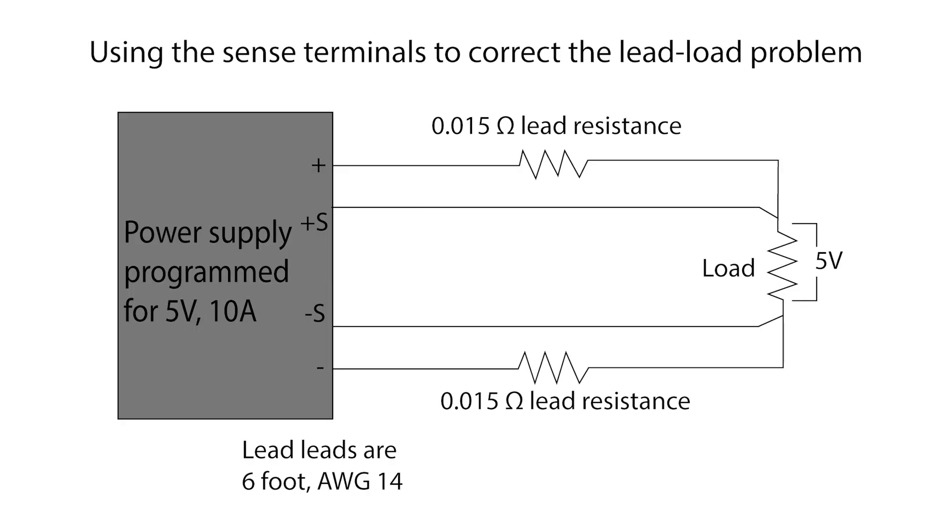There are two sense pins in the auxiliary connector used to compensate for power losses in long load cables. So you can get output voltage regulation at the load rather than at the converter's output terminal. The remote sense feature can compensate output voltage drops of up to a half volt.